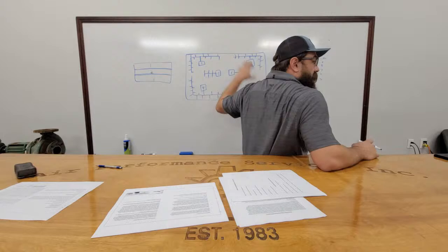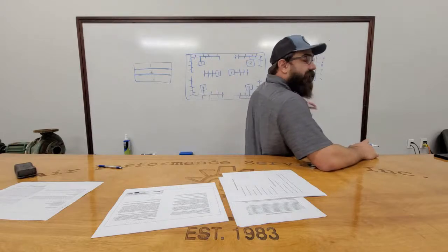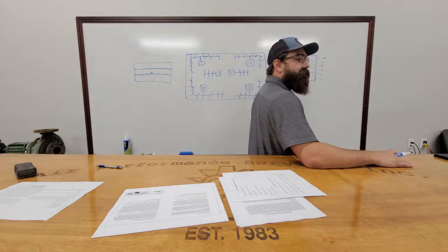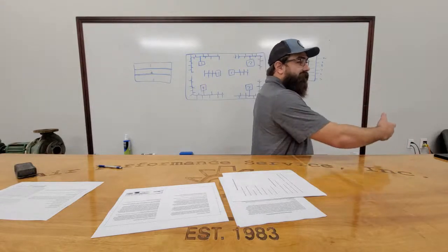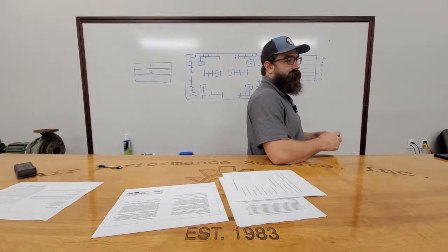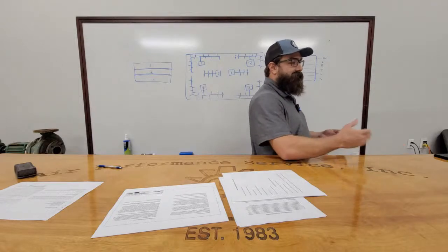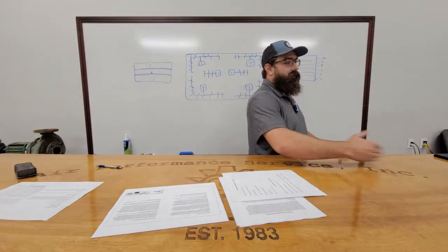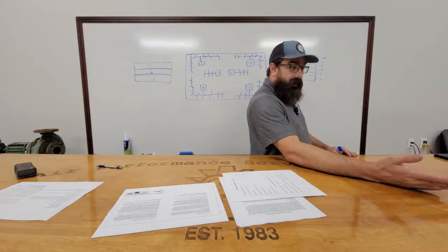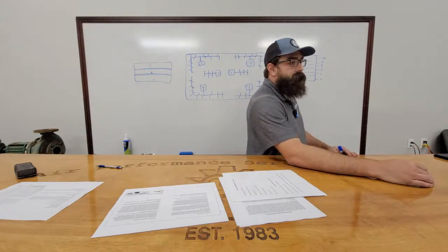We look through all these variables and determine what has to happen in order to start that building by 8 o'clock to have it at temperature. So if it's super hot outside, it's going to start earlier. We call it optimized start stop, which is what the algorithm is called. You're optimizing the time you start your equipment in order to be at set point by the time it's occupied. So hotter, yeah. Would you ever use the derivative for a situation like that?